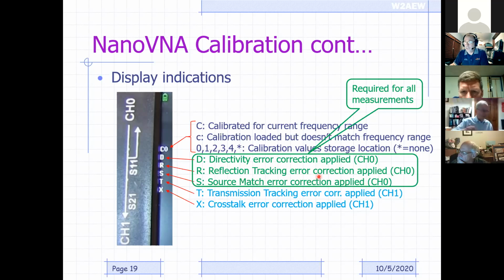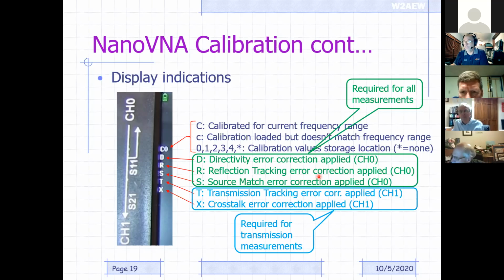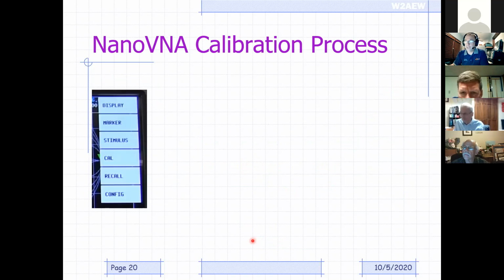If you're only making reflection measurements, like looking at an antenna or something like that, you don't need the other two. So you don't have to do the calibrations associated with the other port with channel 1. They're only required when you're making transmission measurements. So it's perfectly valid if you're only going to use it as an antenna analyzer, just do the first 3 steps of the calibration process and ignore the other 2. Okay. So how do you do the calibration?